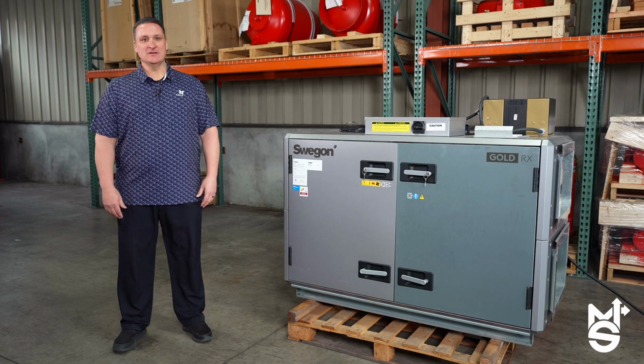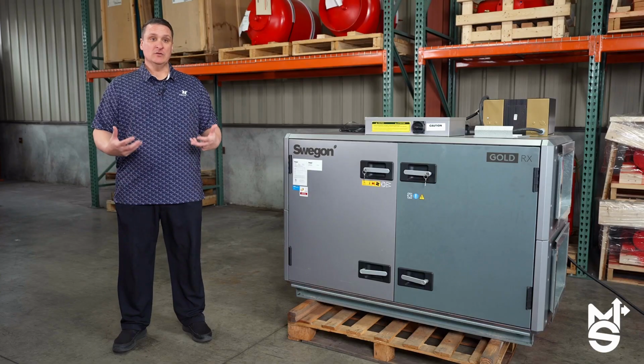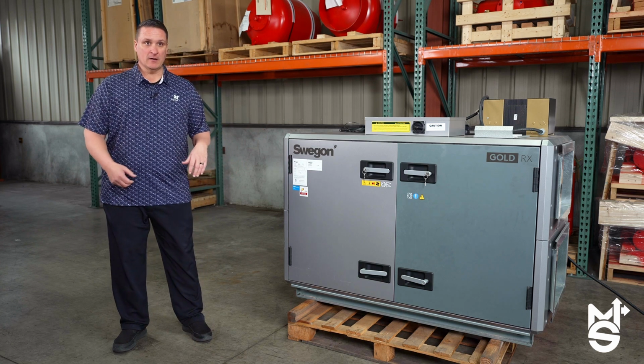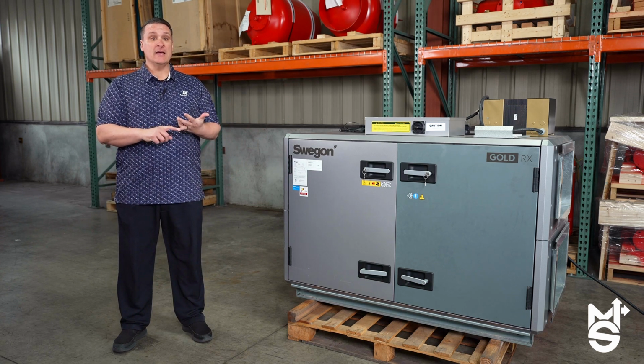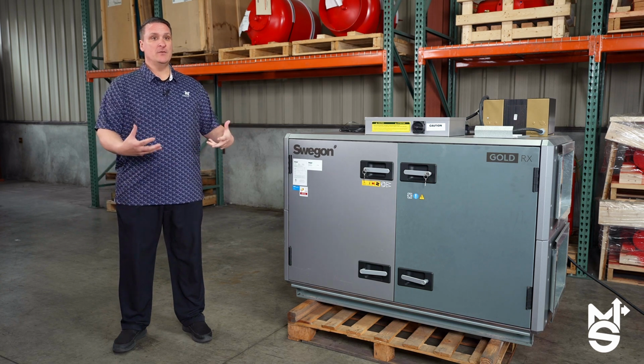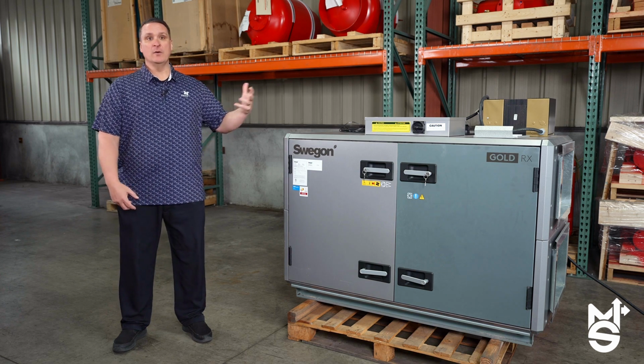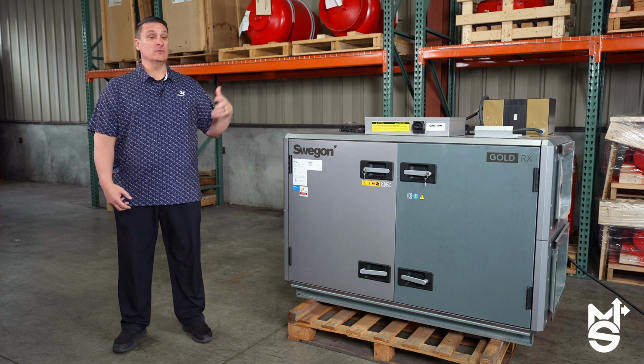Let's talk about the manufacturing standards of the Swegon Gold RX ERV. The Swegon Gold is designed to be very modular and scalable. The Swegon is available in sizes from 500 CFM all the way up to 18,000 CFM. The units are sectional. The main section, as you see here, includes the fans, the filtration, the energy recovery wheel, and the control system. Other modules are like building blocks on the main section. We can add coils. They could be electric coils, hydronic coils, refrigerant-based coils. We can add dampers. They can be indoor dampers, outdoor dampers if we're going to install the unit on a rooftop. All these sections become plug and play in the Swegon ecosystem. So whatever section we're adding, it's just a building block which we plug into the control system and becomes readily available for control.